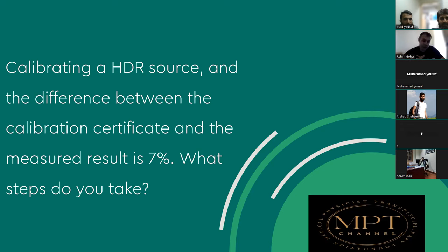How many of you are doing HDR? I remember at AKU, we used to verify definitely the air kerma strength. And the question is, the difference between your certificate and your measured one is 7%. What are you going to do? Well, fortunately or unfortunately, we haven't found this kind of discrepancy yet. So we may not have experience if we got this kind of error.